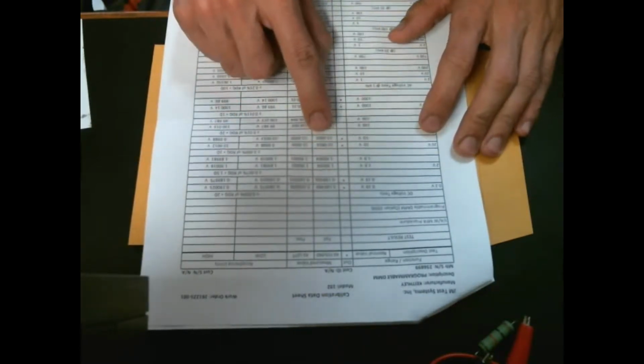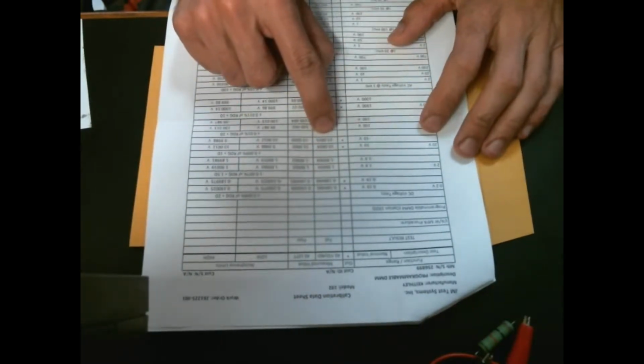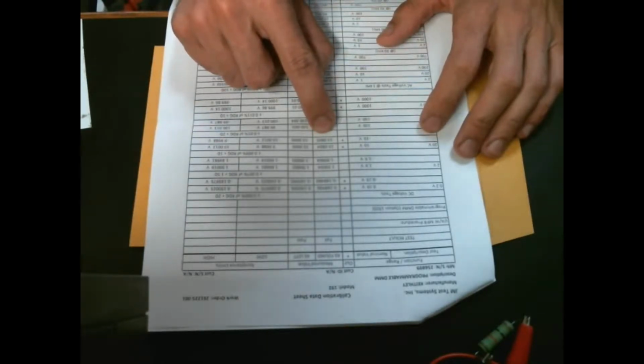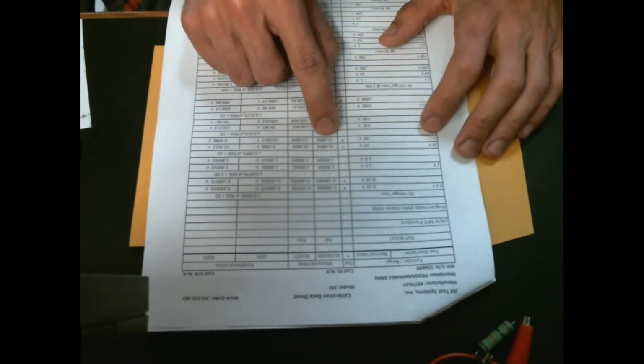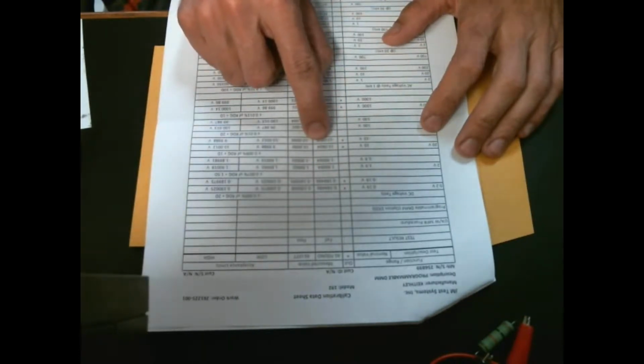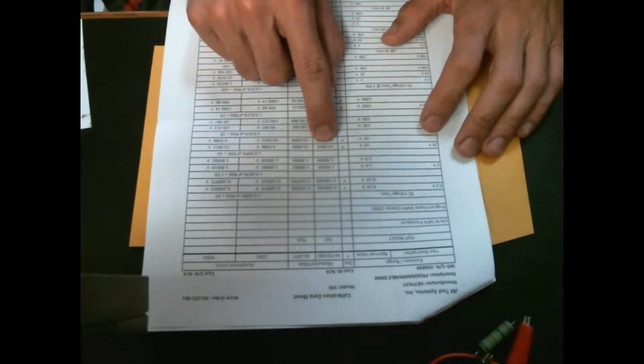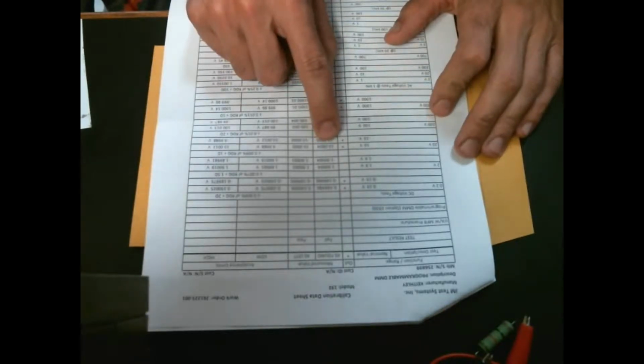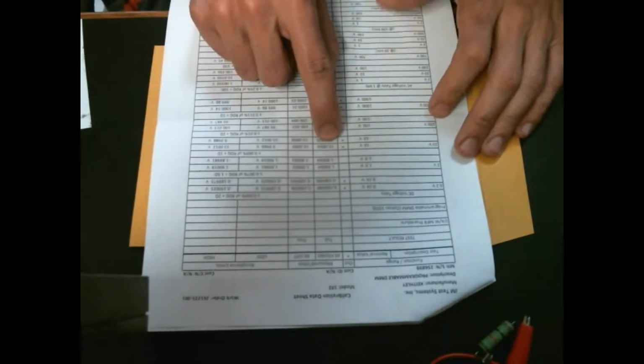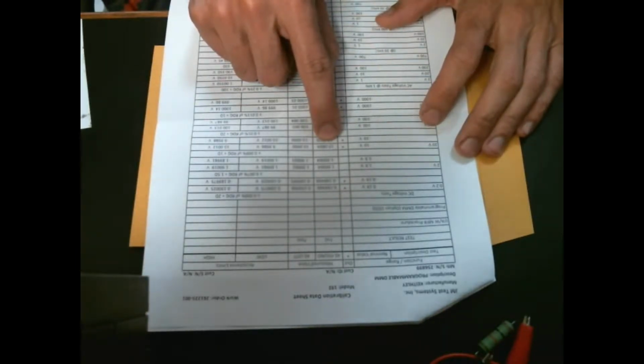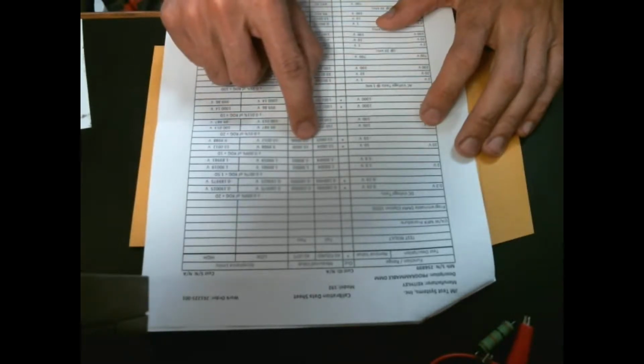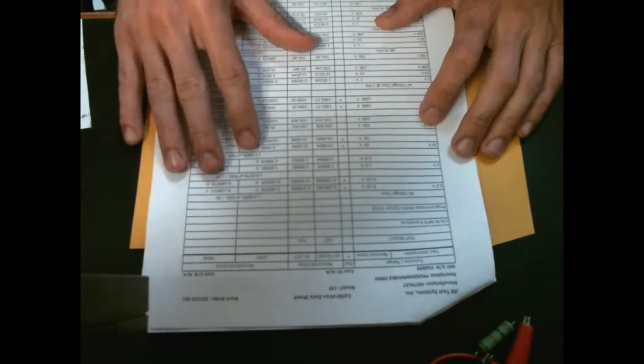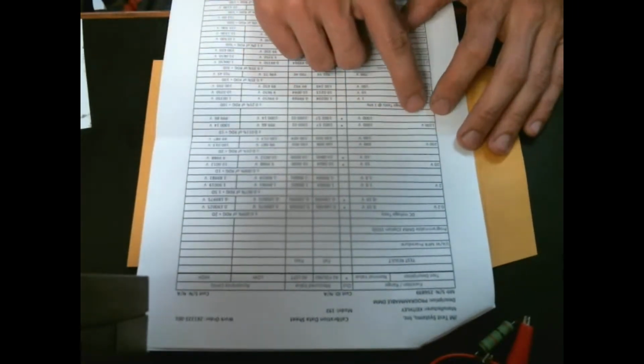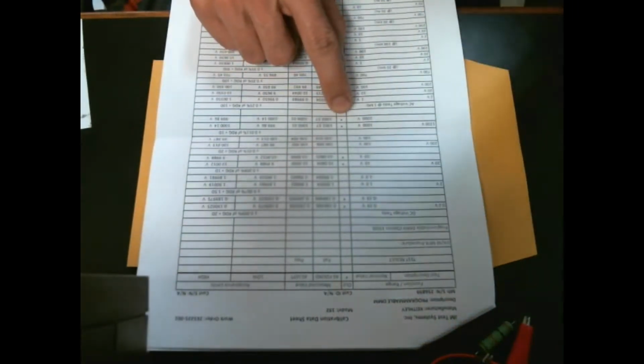20 volt range, this is the range that I knew was very badly off. And as you can see, at 10 volts, it was reading 10.08. That's bad for a 3.5 digit meter, and I have a 6.5 digit meter that was reading that roughly. But they brought it right in the spec. I mean, dead on 10 volts. That is awesome.